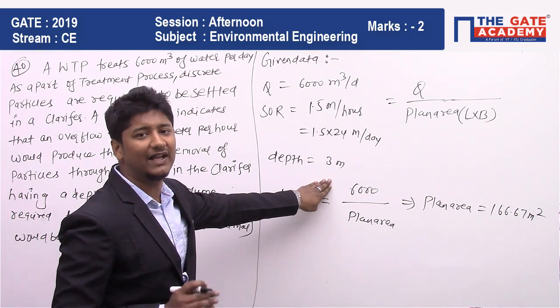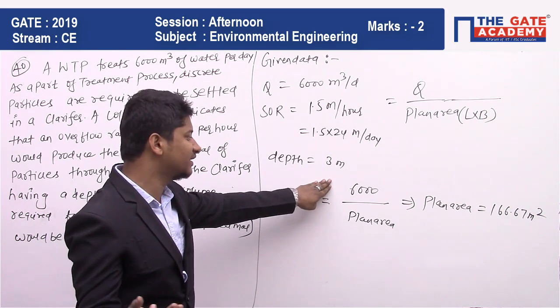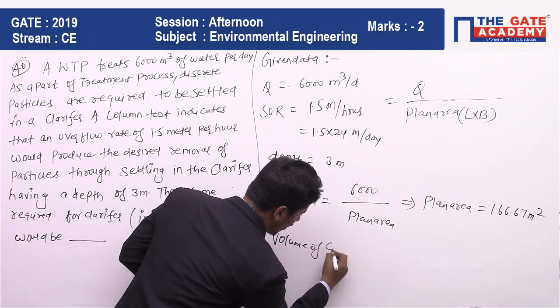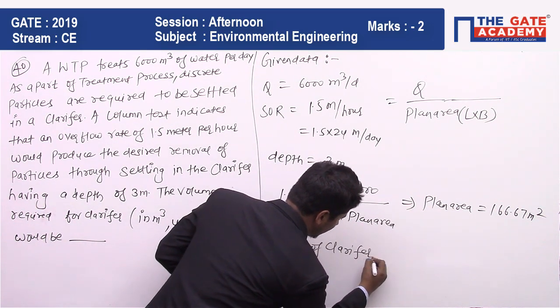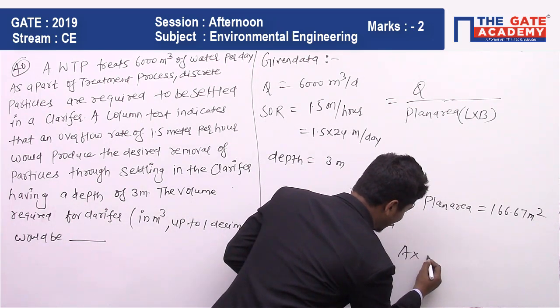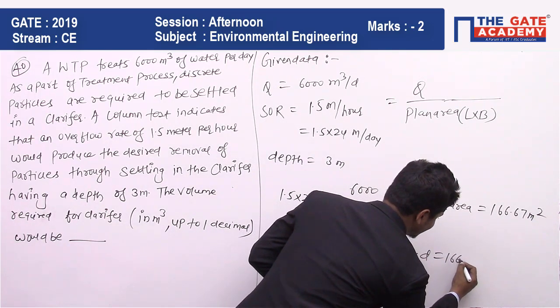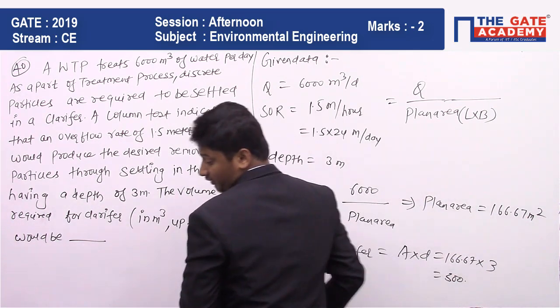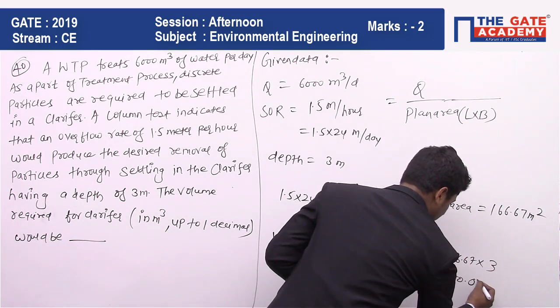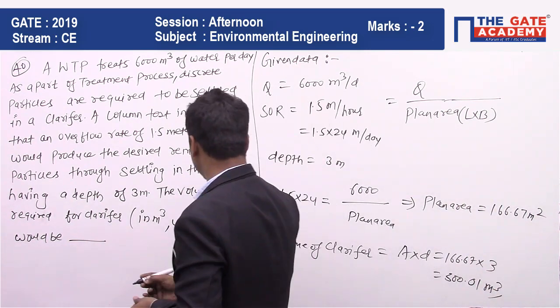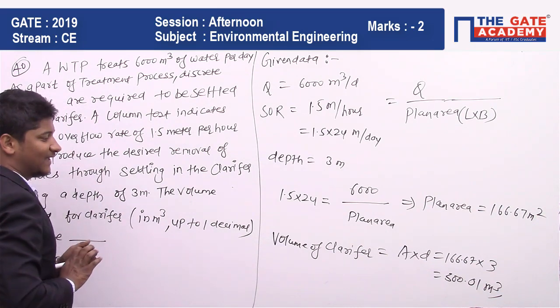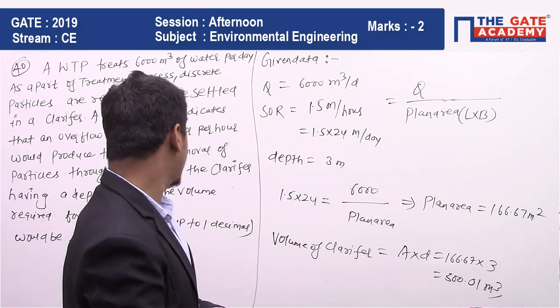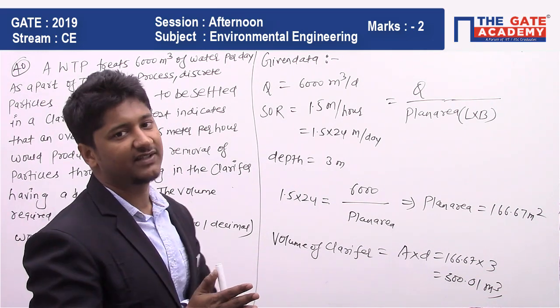The depth of the clarifier is 3 meters and they are asking the volume of the clarifier. Volume = area × depth = 166.67 × 3 = 500.01 meter cube. They are asking the answer up to one decimal place, so the answer is 500.0 meter cube.